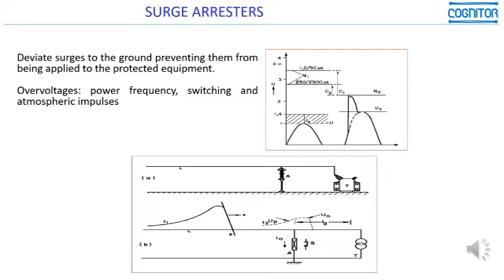If one pulse, for example one atmospheric discharge, drops in the line and comes walking along the line in the direction of the transformer, you have in any point of this circuit the value of this surge, this overvoltage caused by the surge, summed up to the normal voltage, the industrial frequency voltage of the line, which is connected to the transformer.